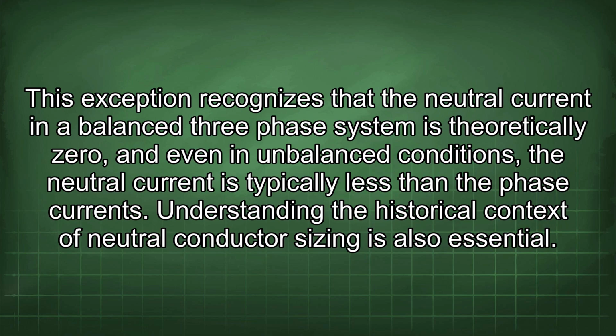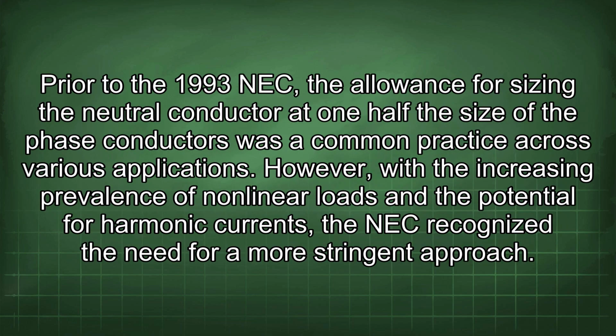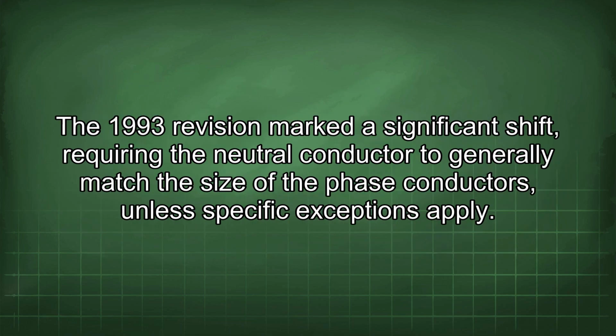Understanding the historical context of neutral conductor sizing is also essential. Prior to the 1993 NEC, the allowance for sizing the neutral conductor at 1/2 the size of the phase conductors was a common practice across various applications. However, with the increasing prevalence of nonlinear loads and the potential for harmonic currents, the NEC recognized the need for a more stringent approach. The 1993 revision marked a significant shift, requiring the neutral conductor to generally match the size of the phase conductors, unless specific exceptions apply.